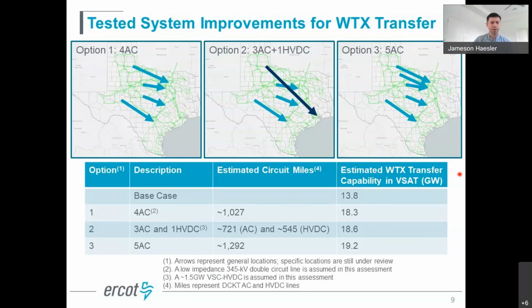So here's an overview of those three options. A couple of notes first: wherever AC is referenced, a low impedance 345 kV double circuit is assumed, and for HVDC references, a 1.5 gigawatt VSC HVDC line is being used. You'll see that all three options do significantly increase the transfer capability across West Texas. And just as a point of reference, we're talking about anywhere from about 1,000 miles up to 1,300 miles of double circuit lines.